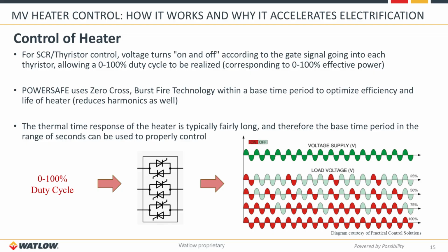That's very important for the longevity of the heater. The more constant we can keep that element temperature, the longer life you're going to get out of that particular heater. If you want to adjust the power levels, then you just adjust the duty cycle associated with how much power you want to input into the system. So if you want to jump to a 75% duty cycle and get 75% of the power output of that heater, you set your duty cycle to 75%.